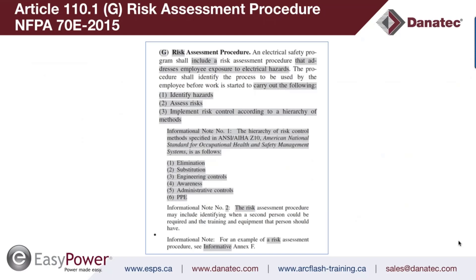Previously, NFPA 70E required an electrical hazard analysis strictly focused on hazards: get PPE on the qualified person and establish boundaries. That context changed in the 2015 edition. The risk assessment procedure now has a substantial change in the 2018 edition. The 2015 article mandates that your electrical safety program shall include a risk assessment procedure that addresses employee exposure to electrical hazards.